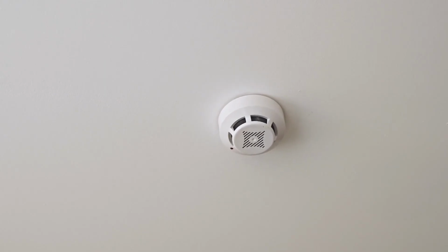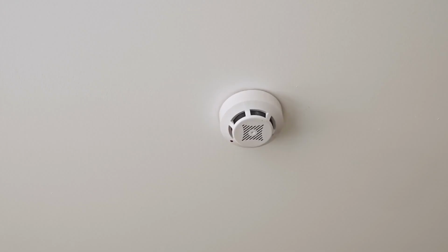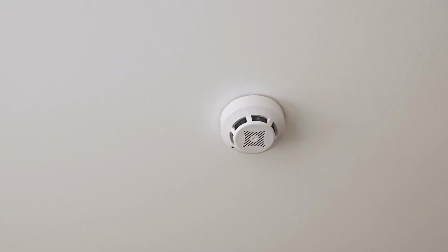So, in summary: gas leak detection systems are mandatory in SCA projects with natural gas or dual fuel boilers. Detectors must be strategically located. Alarms must shut down fuel systems and notify the fire alarm and BMS. And systems must meet strict NYC code and FDNY approval.